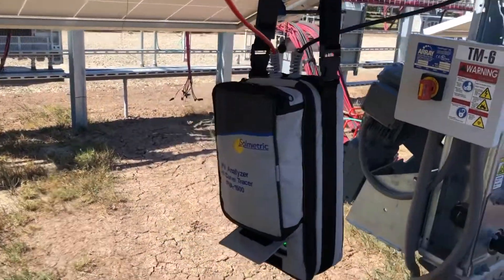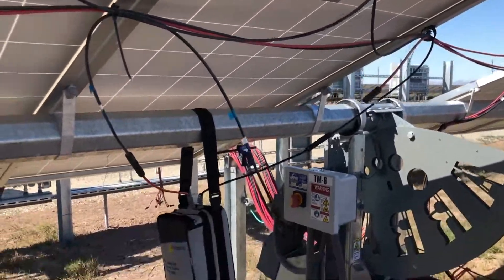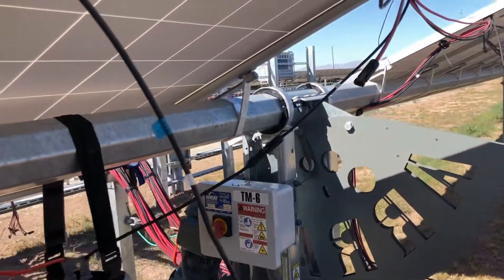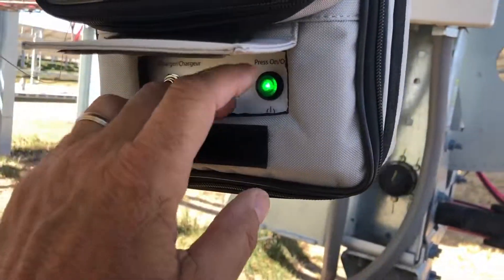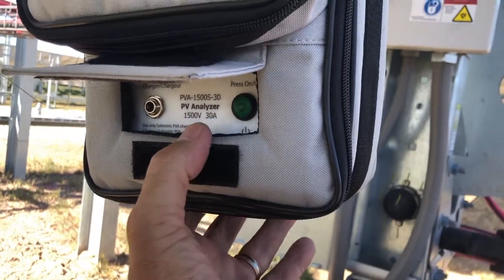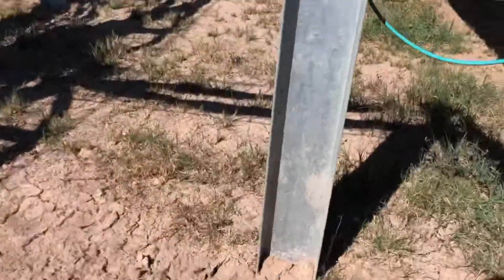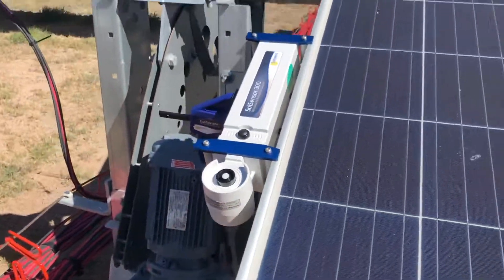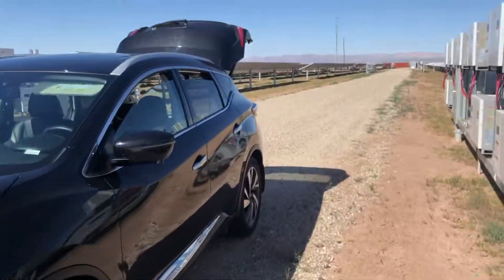The Solmetric PV 1500 analyzer is set up, close to the module we're testing. Now I'm going to turn these guys on and see if I can get them communicating with the laptop. This one is on — it's blinking green, I think it's going to try to create a network between that and the SolSensor. The red light is on — yep, SolSensor confirmed. Now I'll open up the PV analyzer software on my laptop and see if they can link up and create a network.